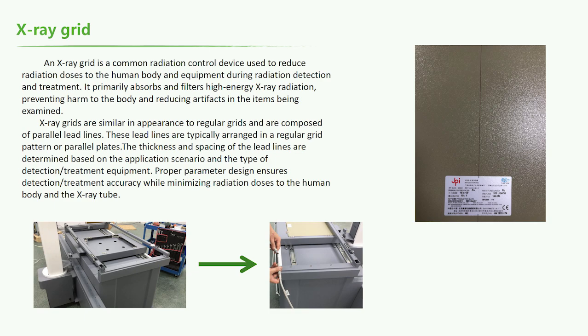X-ray grids are similar in appearance to regular grids, and they're composed of parallel lead lines. These lead lines are typically arranged in a regular grid pattern or parallel plates. The thickness and spacing of the lead lines are determined based on the application scenario and the type of detection or treatment equipment. Proper parameter design ensures detection or treatment accuracy while minimizing radiation doses to the human body and X-ray tube.